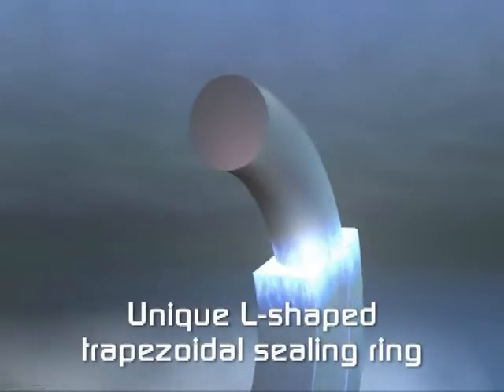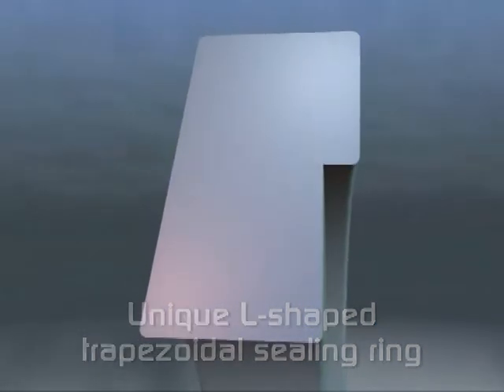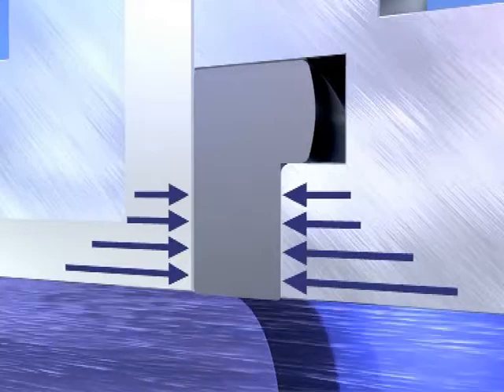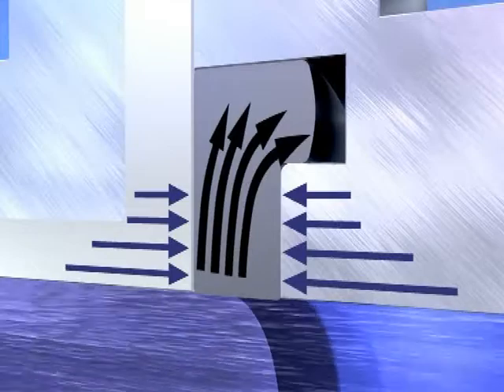KROHNE has overcome these problems with Optiflux 6000 and its L-shaped trapezoidal sealing ring. When the meter is fitted, the seal is compressed. The pressure on the wider part, near the inside of the tube, is higher than on the narrow side further out. Therefore, the sealing ring can only move outwards, away from the pipeline.